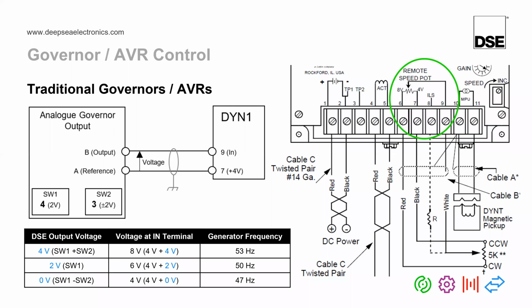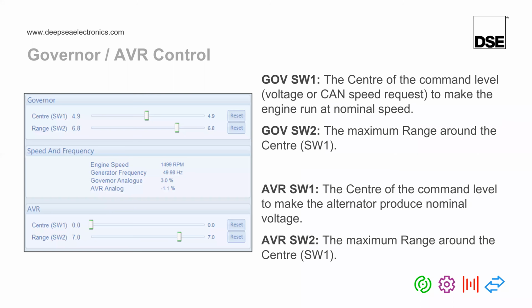So I know I've mentioned here as well about switch 1 and switch 2. Again, we'll cover them in more detail as we go through the presentation. But just to show you where those are, they're not actual physical switches on the DeepSea module. They're actually sliders in PC software. Effectively, the best way to think about it, as I tried to allude to earlier, is that switch 1 is the center command, or how much voltage the DeepSea module needs to produce to make the governor or AVR run at nominal frequency or voltage. And switch 2 is just how much voltage the DeepSea module needs to add or subtract from the switch 1 setting to make it run at minimum or maximum speed.